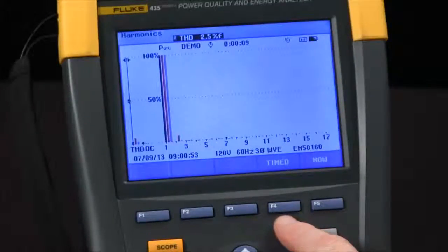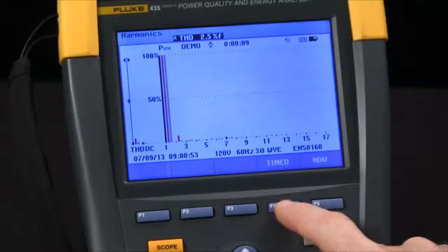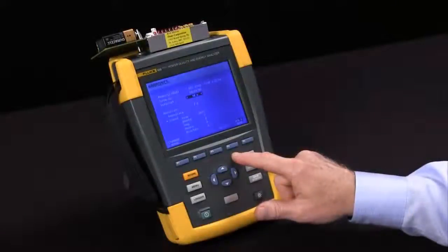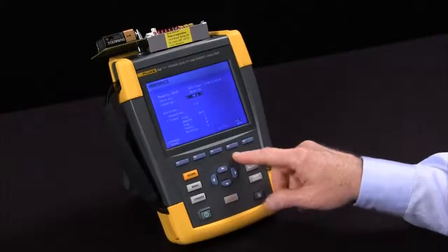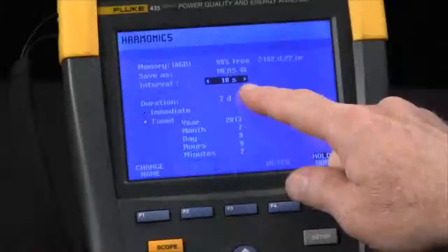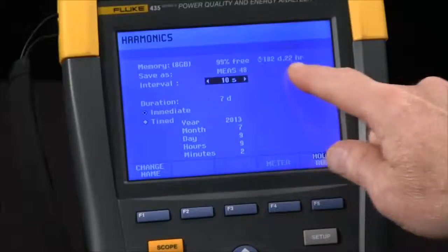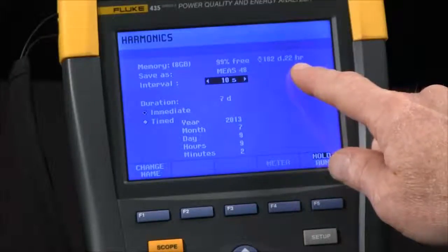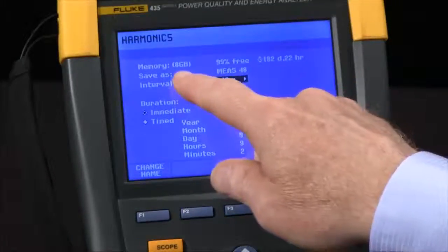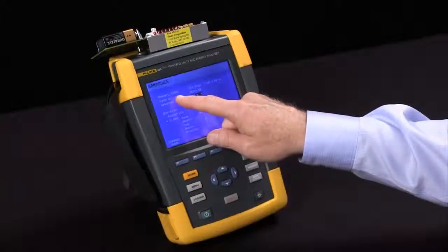Now I have the option to do a timed test. This is very helpful for determining file size when I'm doing trending. Right now with the default 10 second interval, we could record for 182 days. That would create an eight gigabyte file, much too large to deal with effectively with PowerLog software.